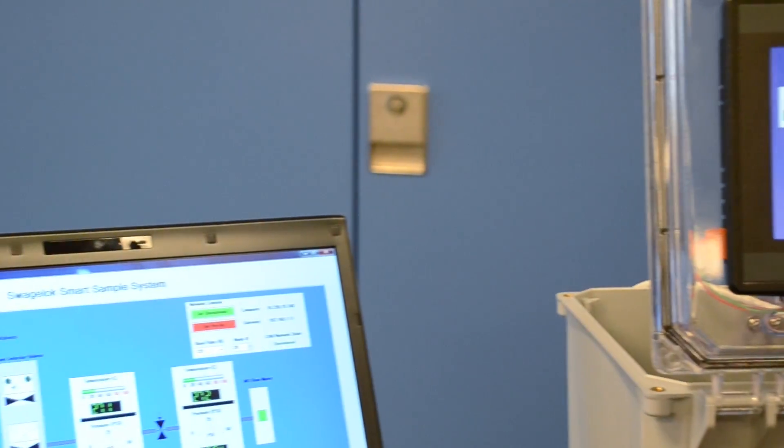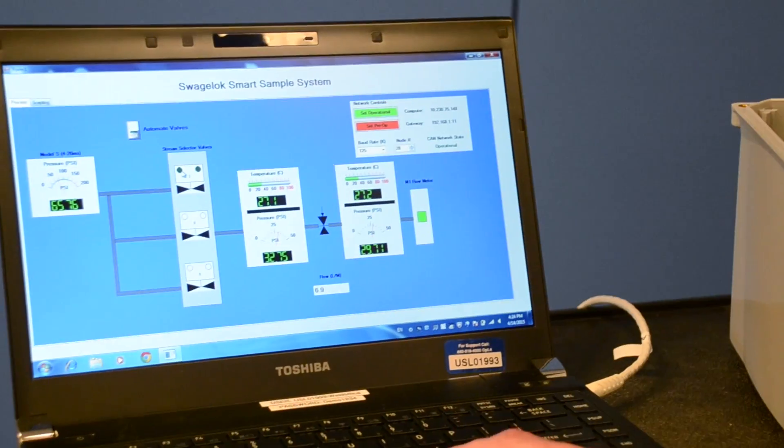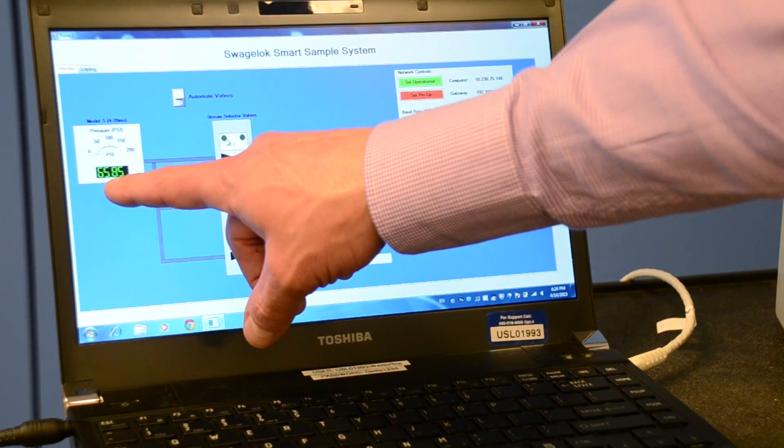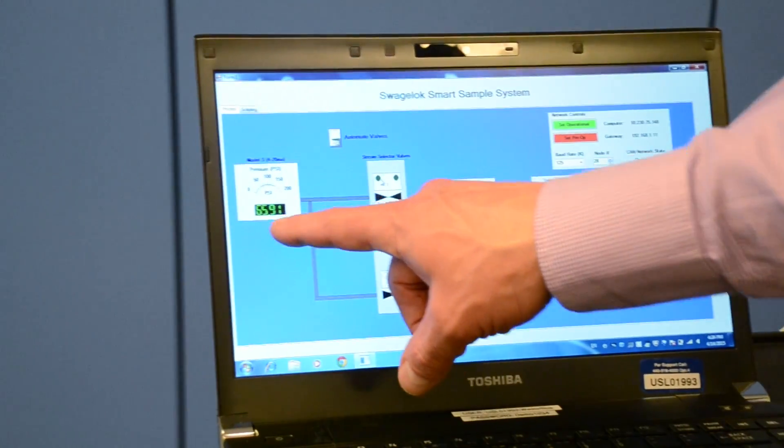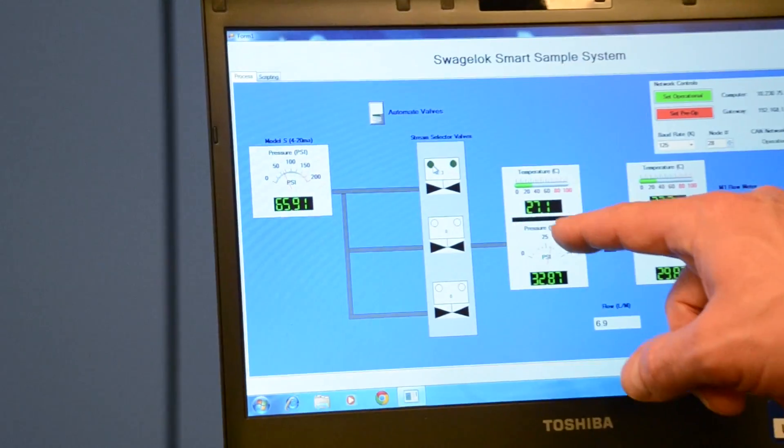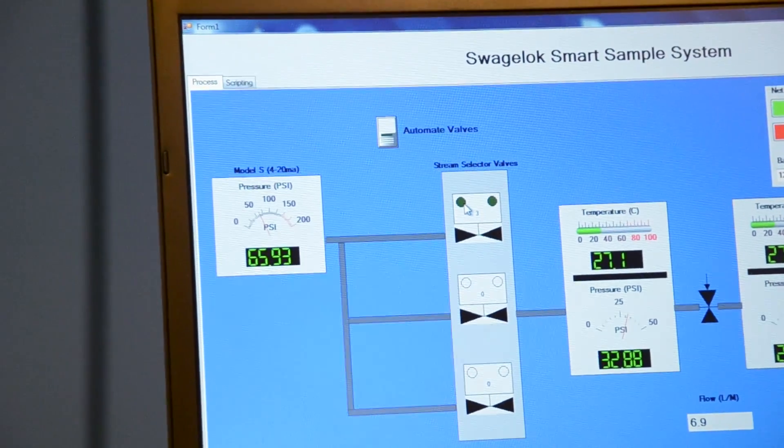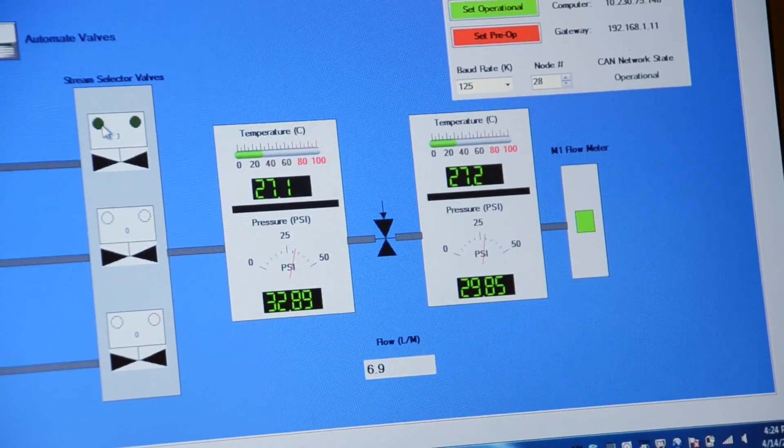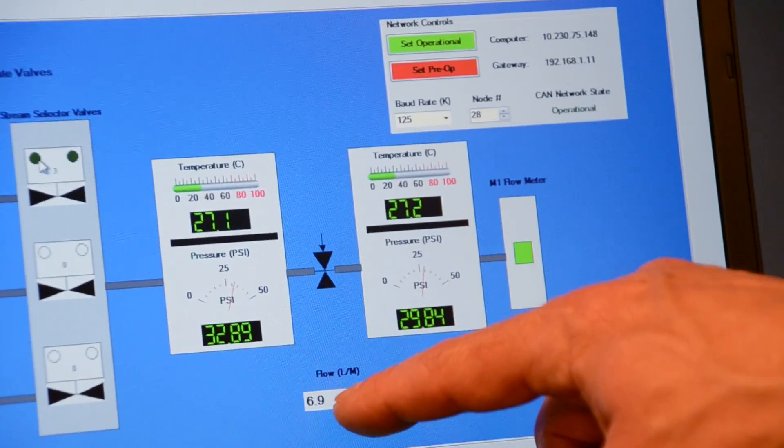Now, as an example of remote control, I'll show you here on this application. A little bit difficult to see, but right there is the inlet pressure from the 4 to 20 milliamp pressure transmitter. Here's your two PTXs, where you have pressure on the bottom, you have temperature on the top. Right there's a measurement of flow.